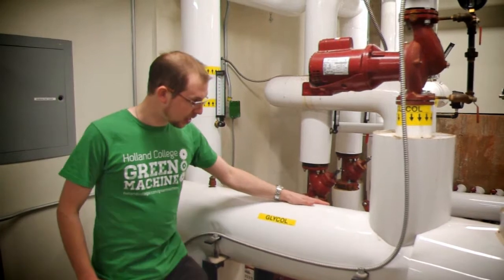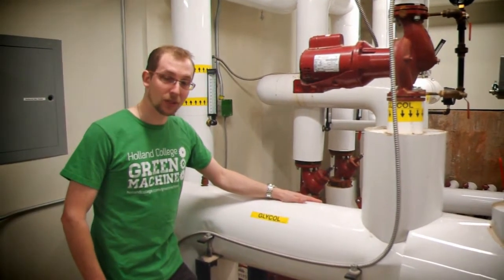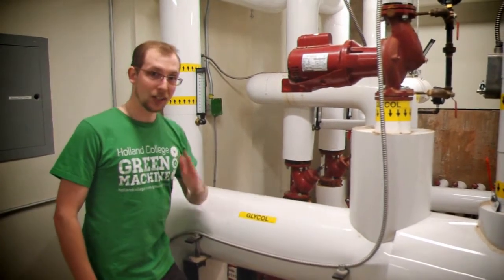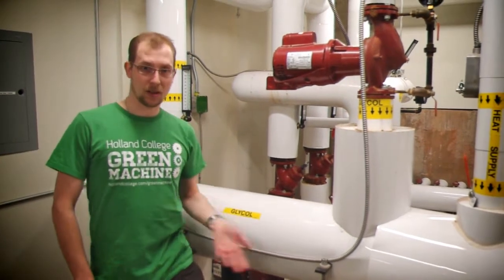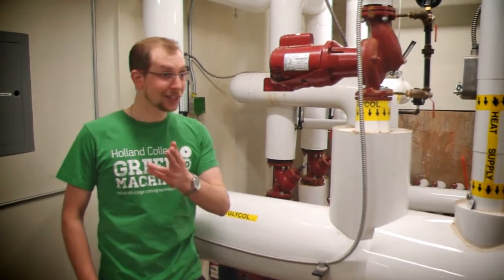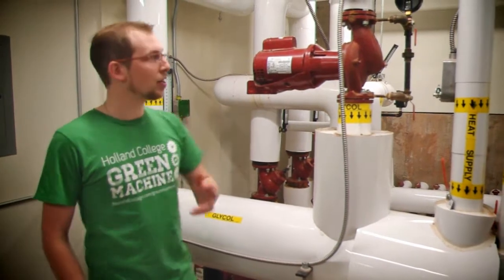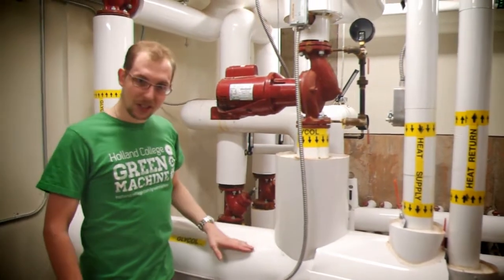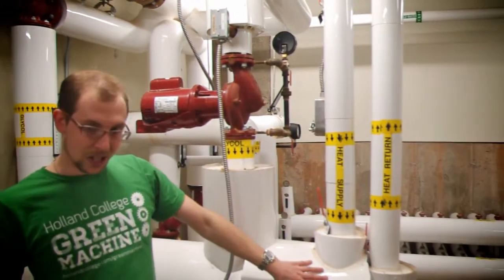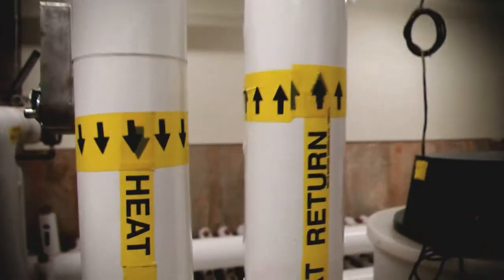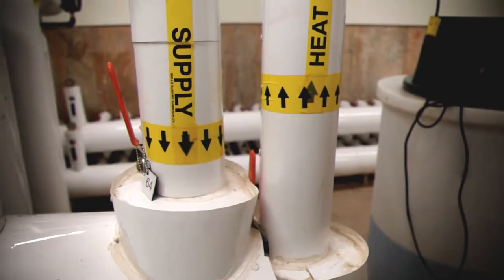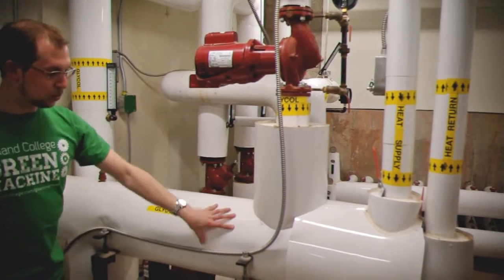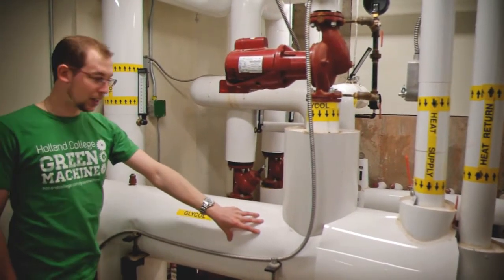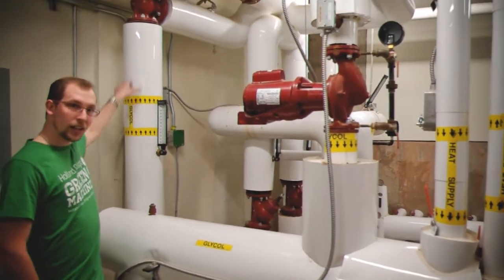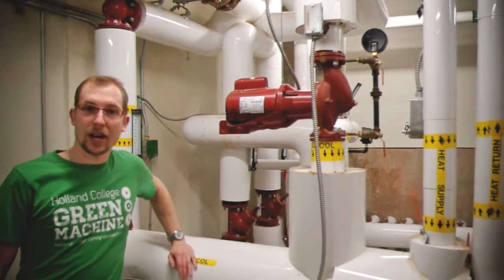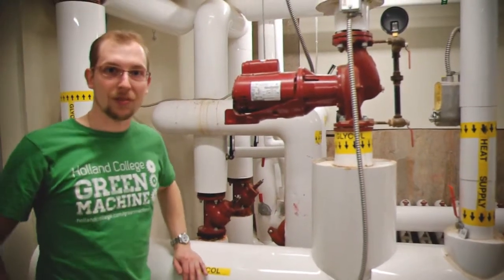So what we have right here is the heat exchange backup system for the ground source heat pump system. In the event that demand for heat can't be maintained by the ground source heat pump, which has yet to happen, that glycol mixture can come right into this heat exchanger, and from here, the heat exchanger is supplied heat from our district heat supply system, and you can see that loop happening right here. So from there, glycol goes through here, being preheated by our district heat, goes up into this pipe over here, and continues on into the system where it goes back to the heat exchangers and continues to provide the building with heat.